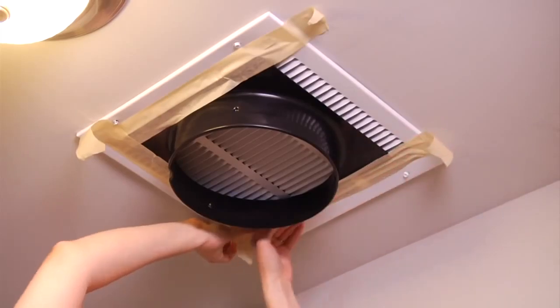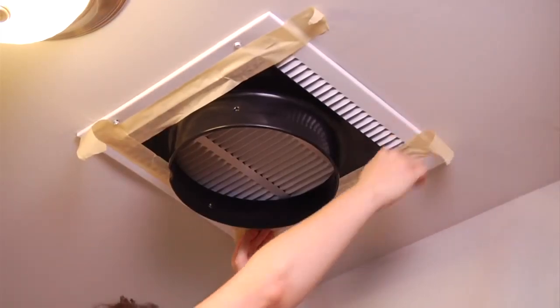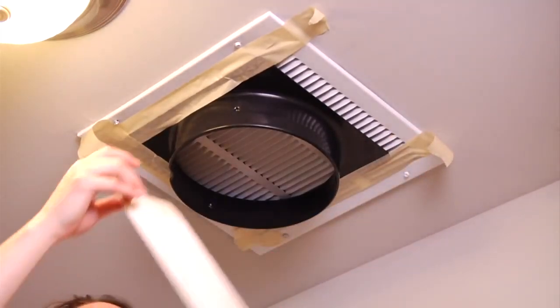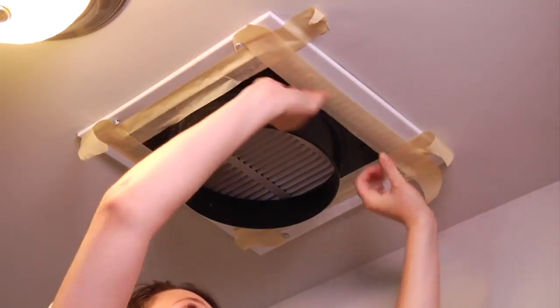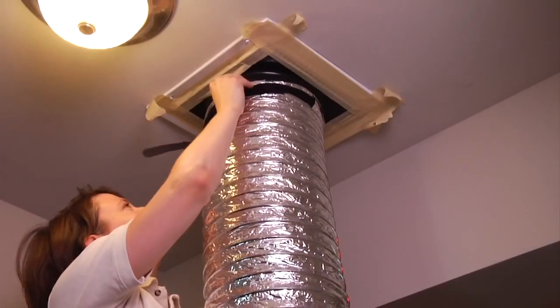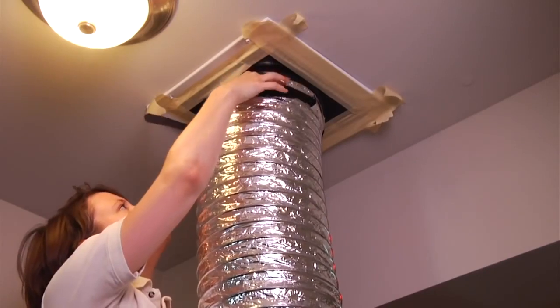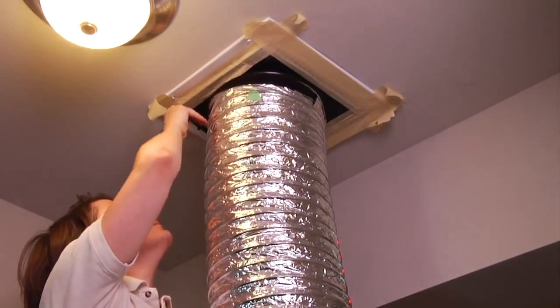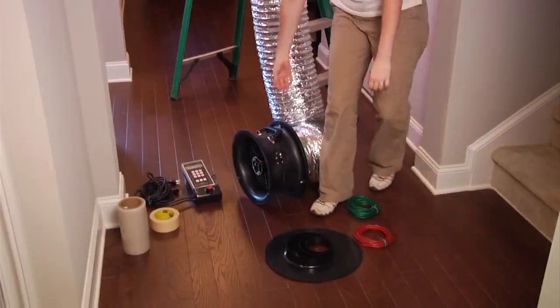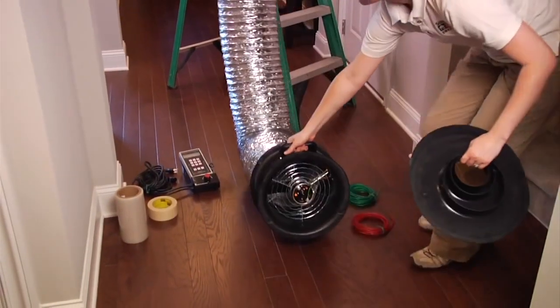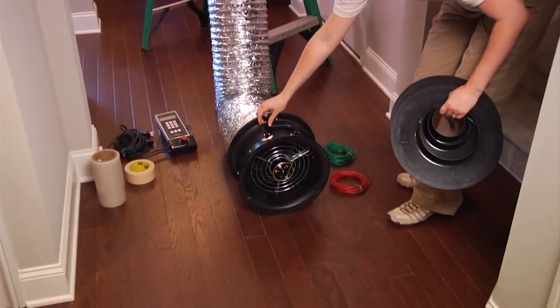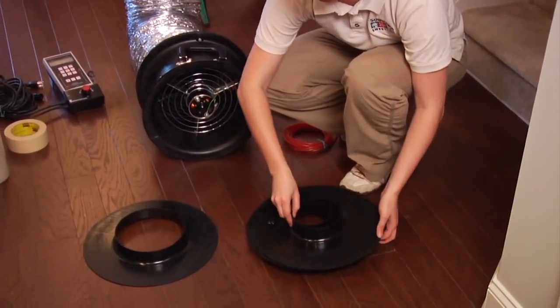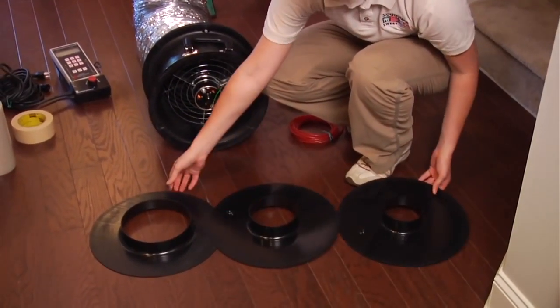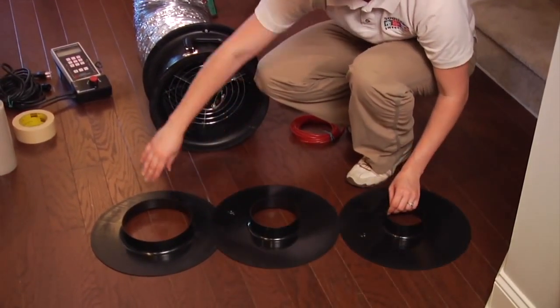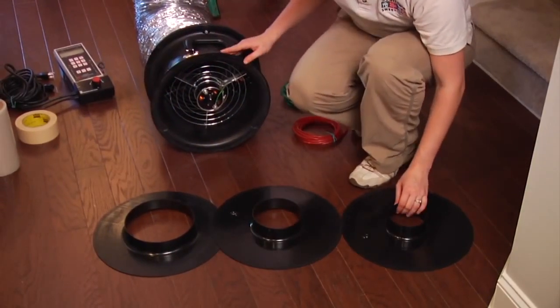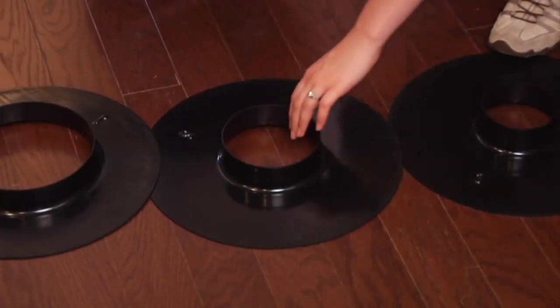and attach the grill adapter of the duct blaster to a centralized return. Seal off any remaining openings of the return grill with tape. Snap on the flexible transition duct or duct trunk using the Velcro strap and extend the duct trunk to its full length so that it is as straight as possible. The duct blaster comes with 3 rings to best match the needed fan flow. Correct installation of the flow ring is important for test accuracy.